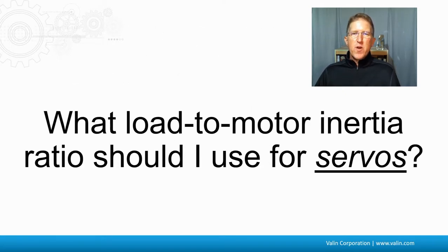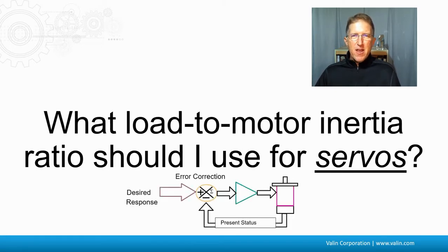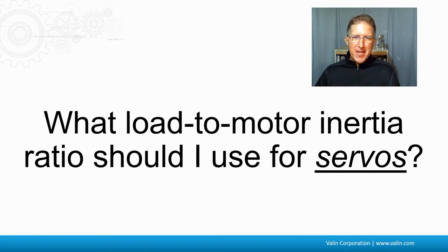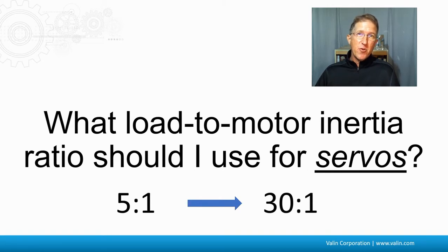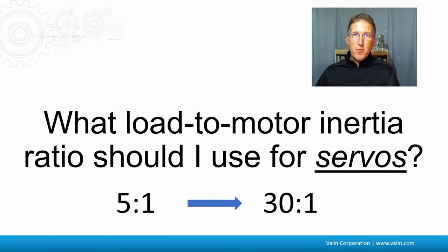For servo motors, servos have an algorithm inside their electronics that has to be tuned — there's a PID loop (proportional-integral-derivative) with math that must be tuned for the application. You'll get different answers from different manufacturers, algorithms, and applications. Some manufacturers aim for 5 to 1; others say 10, 15, or 20 to 1. I've always used 20 as my guideline, but some drives have algorithms good enough to target 30 to 1. If you want the best servo performance, go for a lower inertia ratio. For reasonable performance, 10 to 30 to 1 is fine.